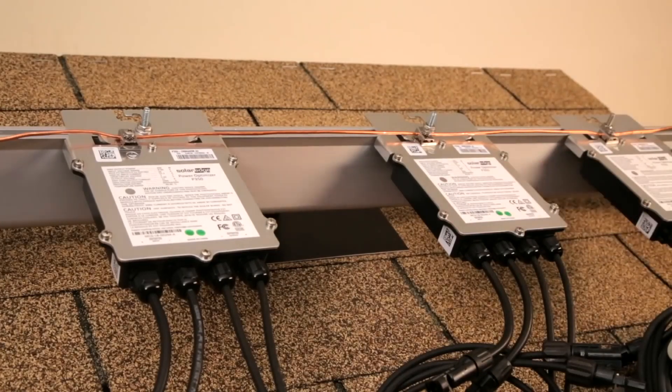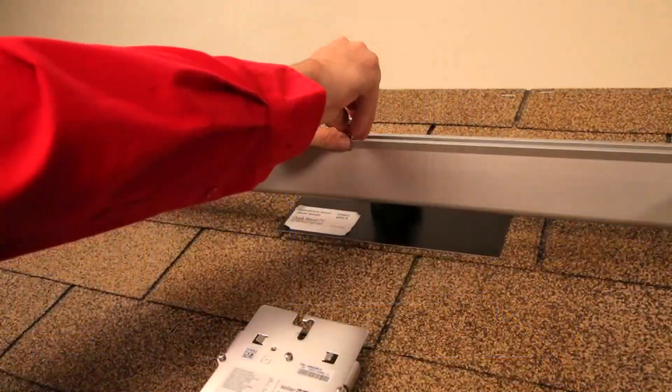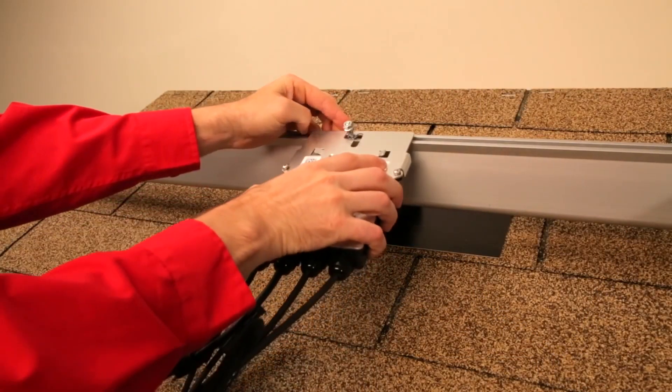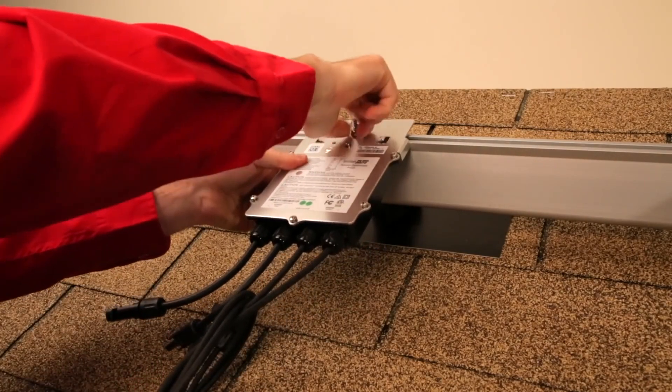With the state of Wisconsin now under the NEC 2017 code for commercial buildings, we have found that the P860 optimizer is the best solution to meet module level rapid shutdown. This is because you only need one power optimizer for every two solar modules.